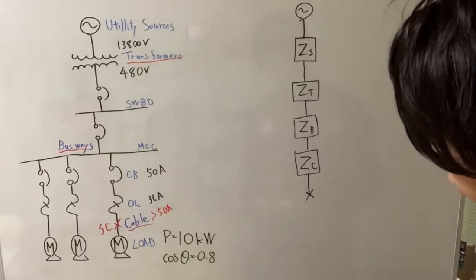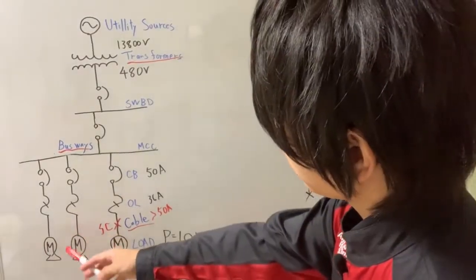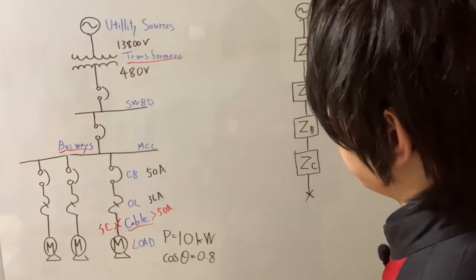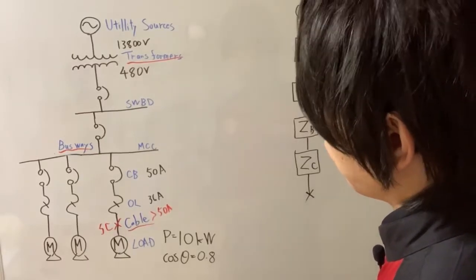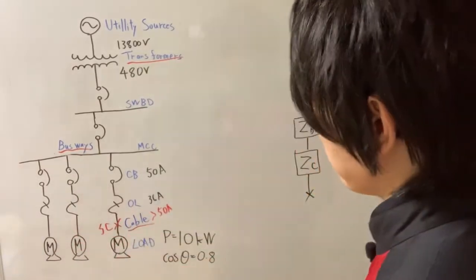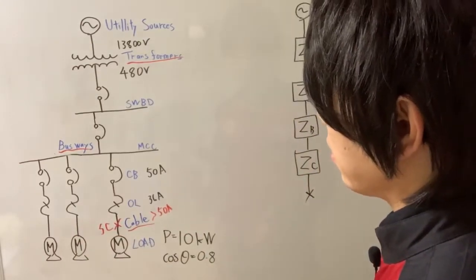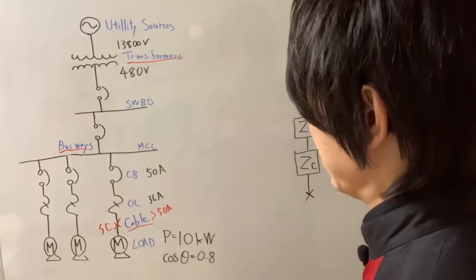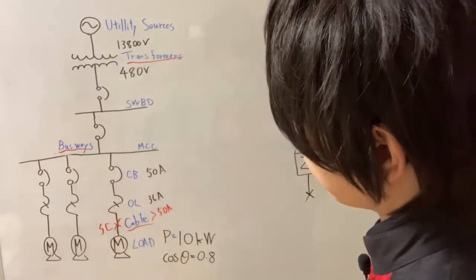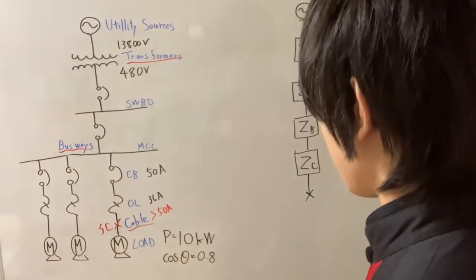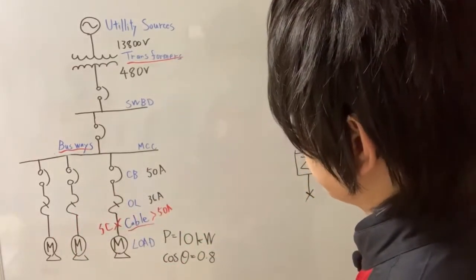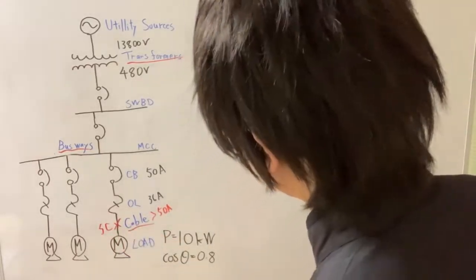By the way, we need to consider about the rotating inertia of these induction motors. You know, the moment short circuit is happening, induction motors could be kind of temporary generators that contribute to increase short circuit current. So we need to add this contributing current to the total short circuit current.